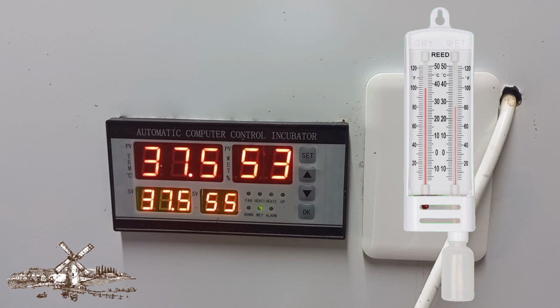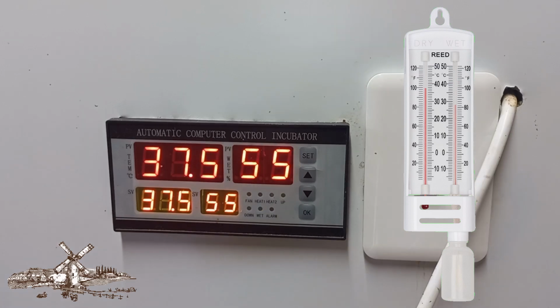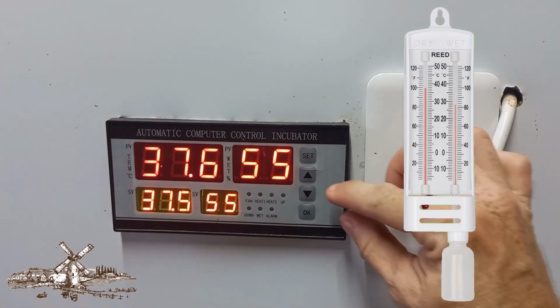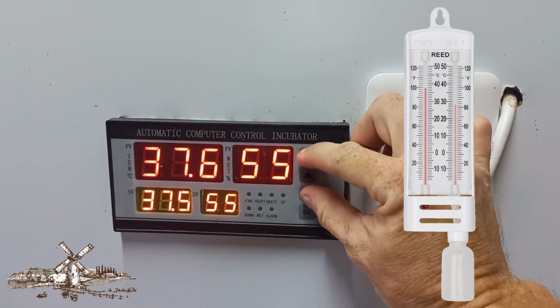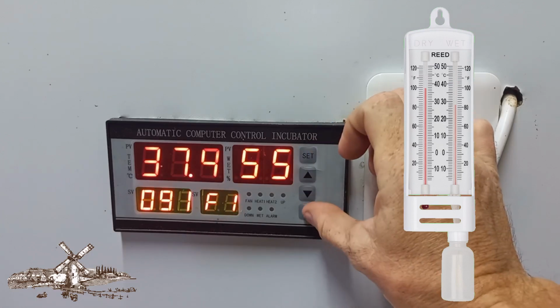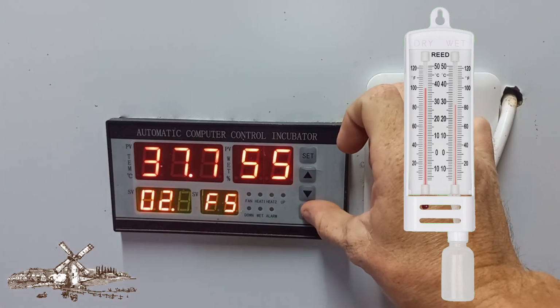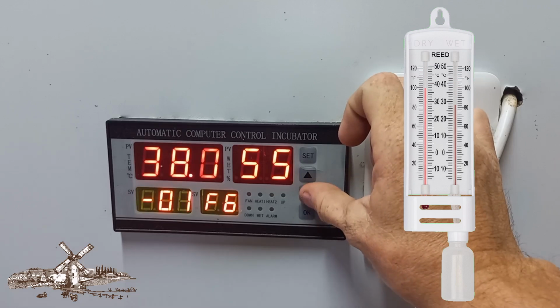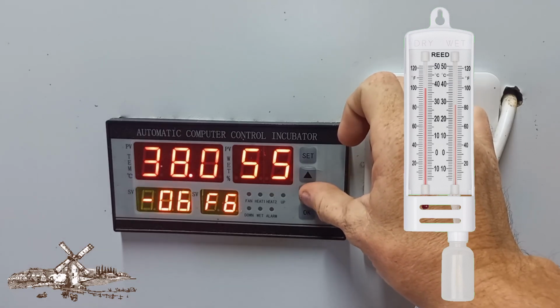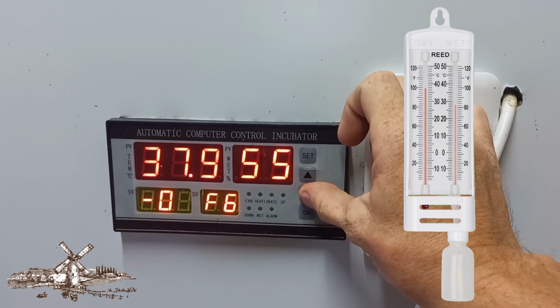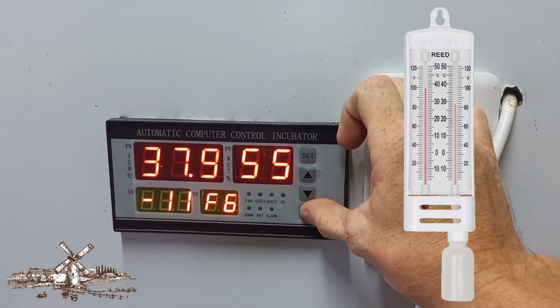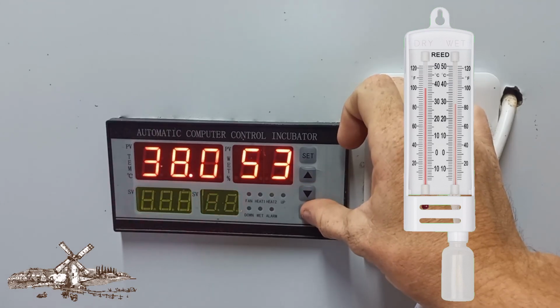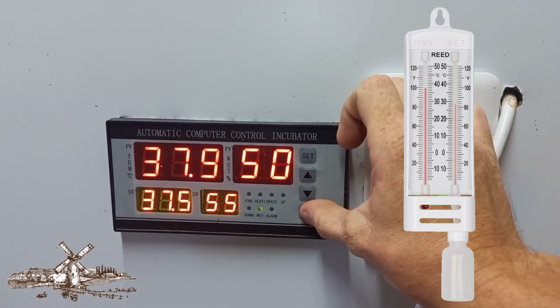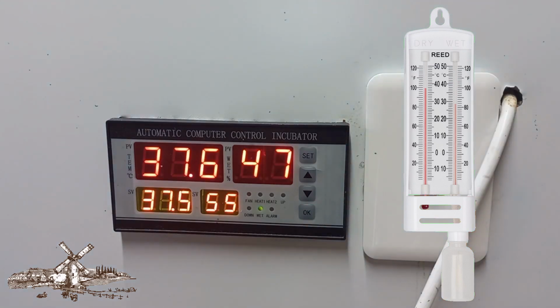Now, in order to change my humidity calibration, I'm going to again push and hold the set button. I'm going to then push the down arrow key. That will go to the F menu. I will push the OK key to go to the F6 value, which is my humidity calibration value. And I'm then going to push the down arrow key so that I can change this value to -11. And so from now on, it will reduce all its humidity measurements by 11%.